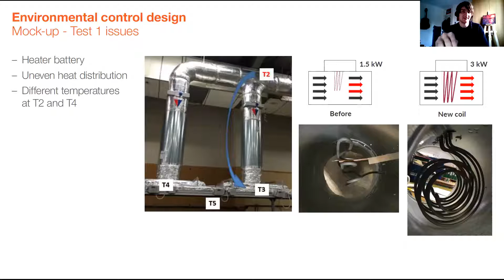Another thing we found was that we had the temperature sensor T2 on the previous slide as the controlling sensor, but because it was within an enclosed duct, it was responding too quickly to any changes in system temperature. So that was causing the system to oscillate very quickly. So we changed the controlling sensor to be a sensor actually within the enclosure. And then another thing we found, as I already mentioned, we were finding different temperatures at different points in the system and at different points in the enclosure. And we felt that was because the ducting design wasn't lending itself to the air mixing before we were distributing it to the two grills.